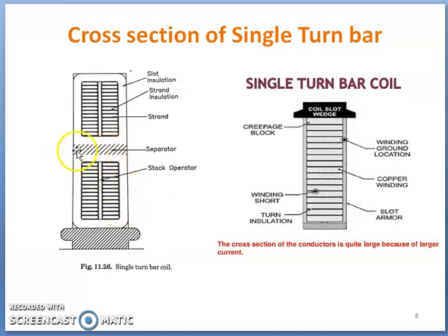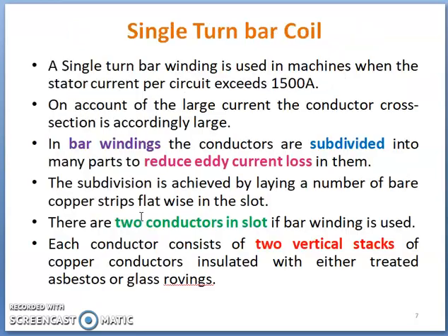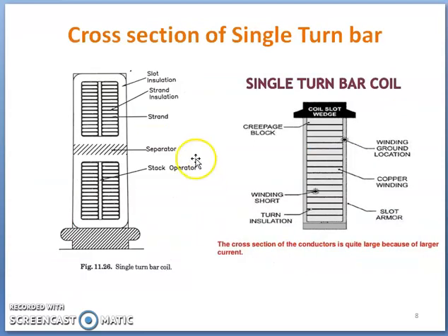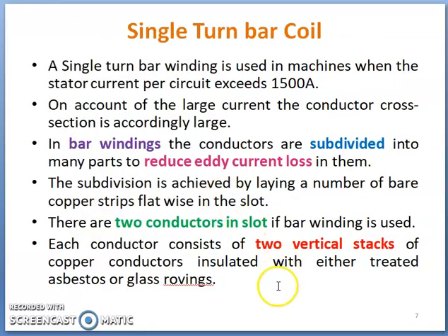A separator is placed between the vertically arranged stacks, along with the main insulation. In case of bar winding, two conductors are put in the slot, subdivided into many parts to reduce eddy current loss. Each vertical stack — there are two vertical stacks — of copper conductors is insulated with asbestos or glass rovings.